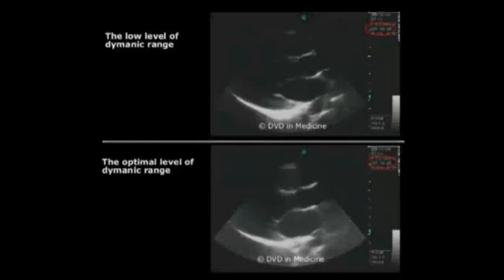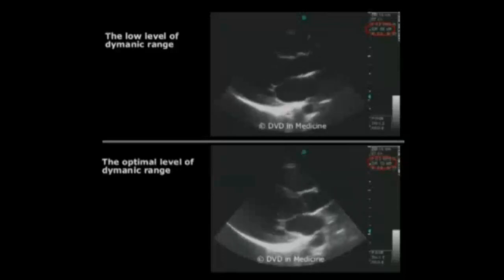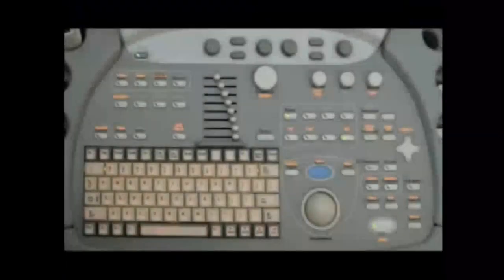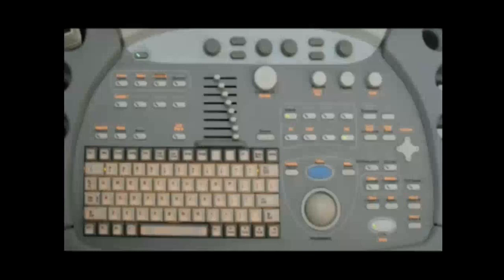The real-time images taken from the same patient at low and optimal levels of dynamic range. The time gain compensation setting. The ultrasound beam is attenuated as it is conducted through tissue. If uncorrected, attenuation will produce a scan that darkens progressively with depth. This is compensated for by the TGC, time gain compensation, amplifier, which progressively boosts the signals from deeper interfaces. This setting operates across the whole image, and so it is only possible to set the best average TGC for each examination.